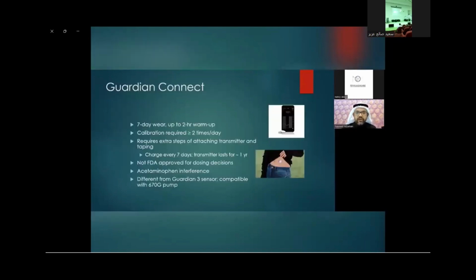Then we have the Medtronic Guardian Connect. Most recently, we got the Guardian Connect sensor, Sensor 4, which does not require calibration. The old one required calibration at least 2 times a day, and it charges every 7 days. The beauty of the Guardian Connect sensor is that it has a transmitter that lasts for up to 1 year, and that is different from the Dexcom transmitter.